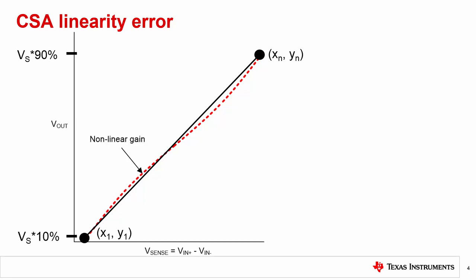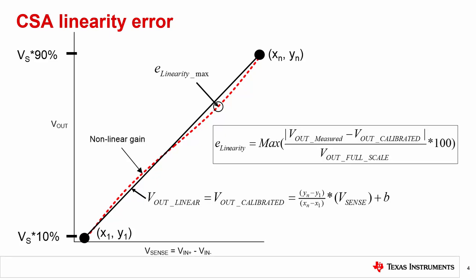For example, if the supply is 5 volts, the two points considered are 0.5 volts and 4.5 volts. Determining the calibrated gain requires calculating linear slope and offset. Linearity error specified in the datasheet is set by the data point that is the furthest from the calibrated gain curve. The percentage linearity error is calculated as Vout measured minus Vout calibrated divided by the full-scale Vout range.